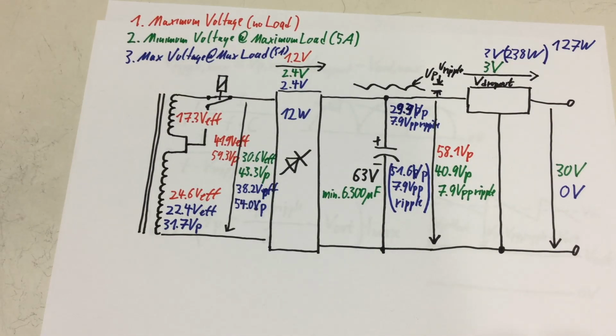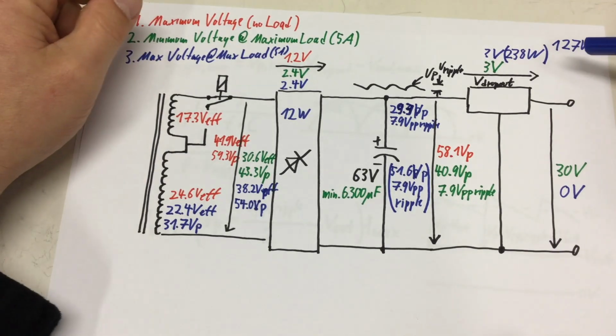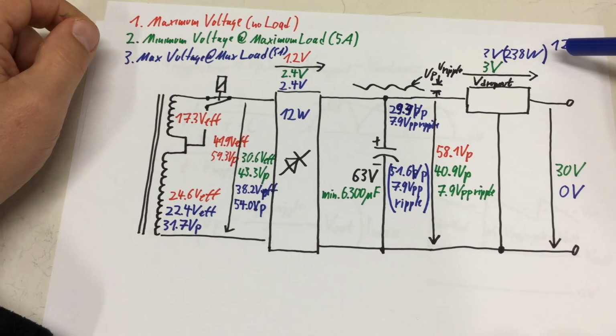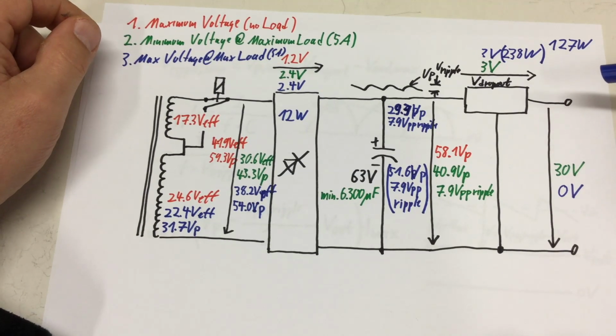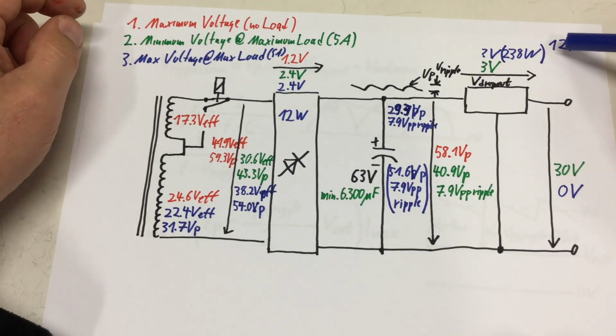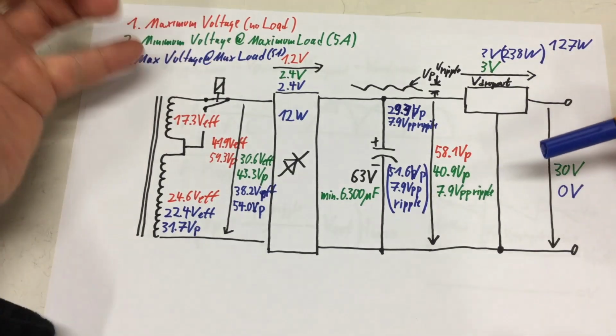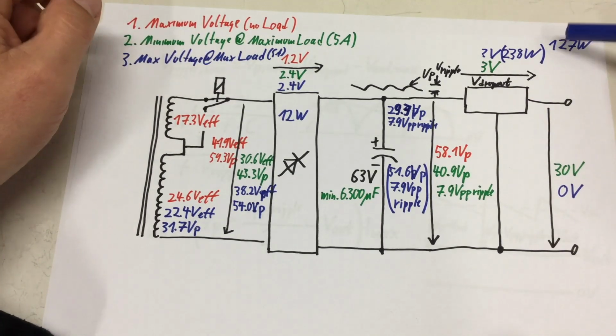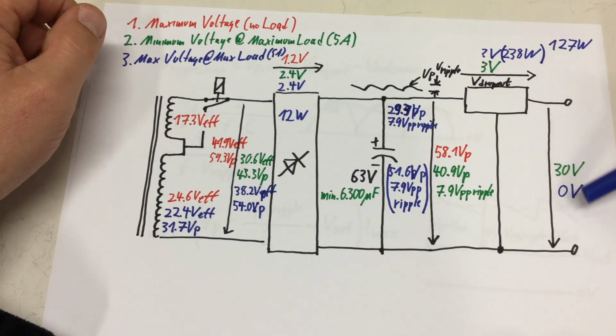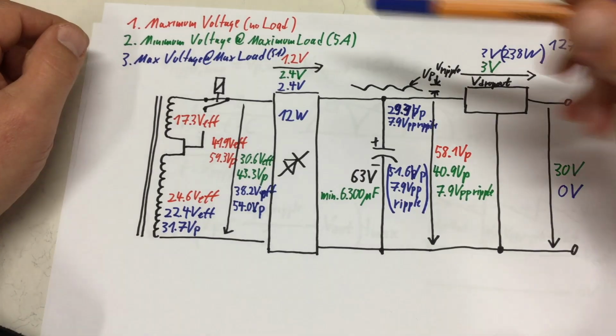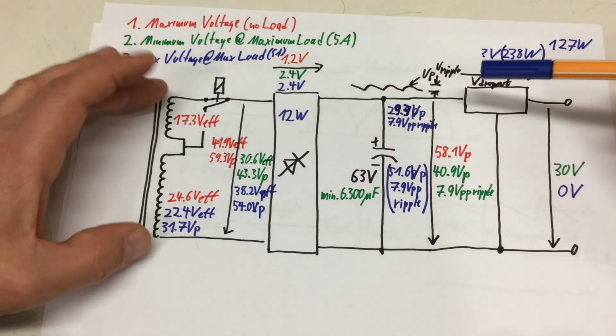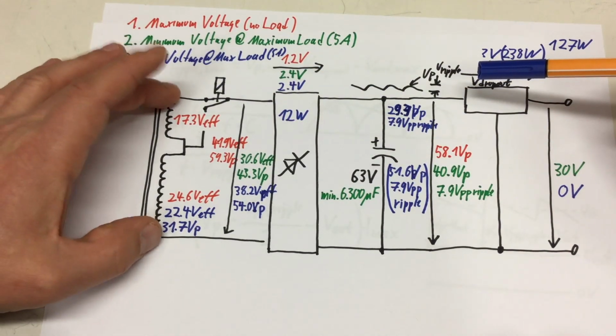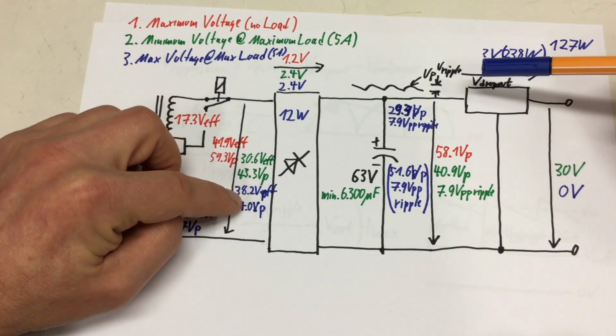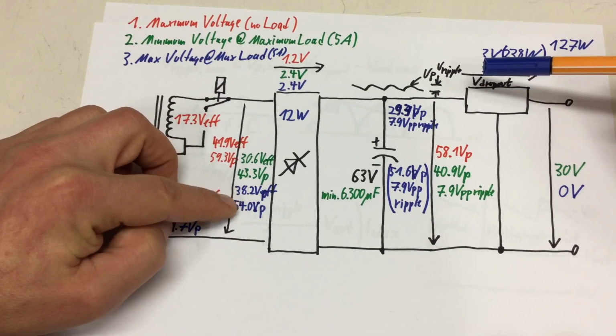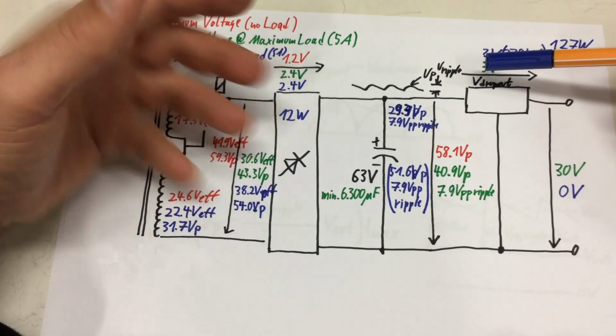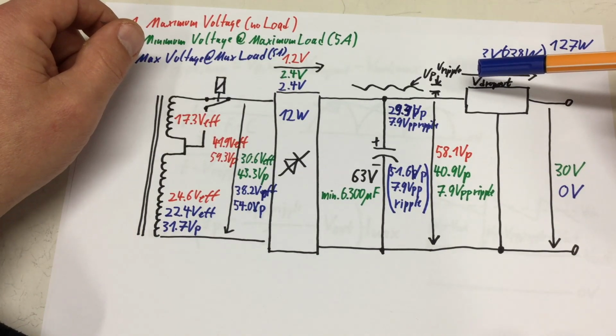Unfortunately we now have to calculate a second worst case, with max load voltage and max load, because at 0 volt output, at some point I have to switch the relay and use both coils again, and then we are at those voltages again. But what is that point?